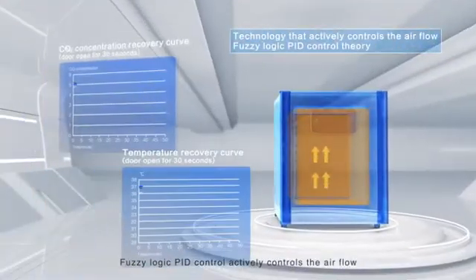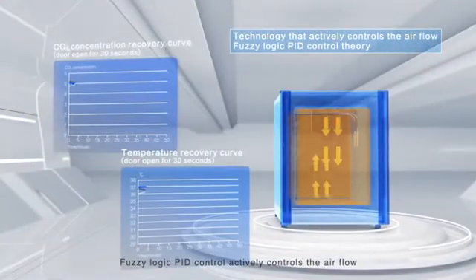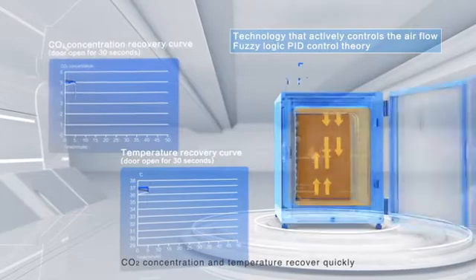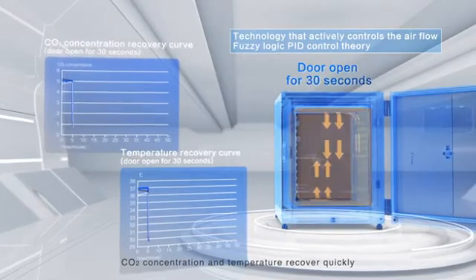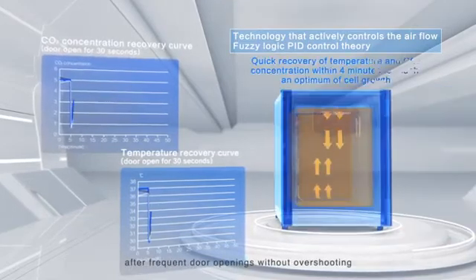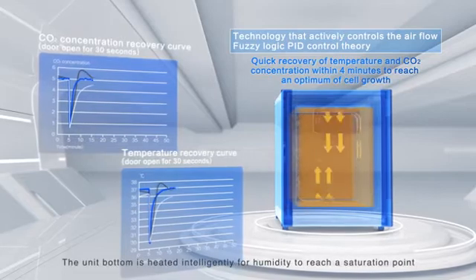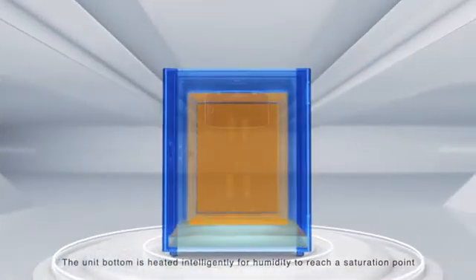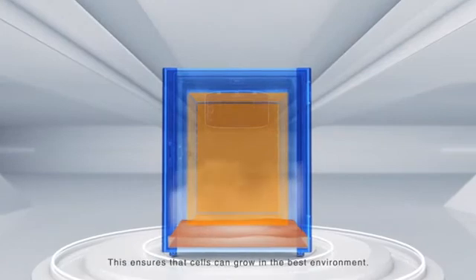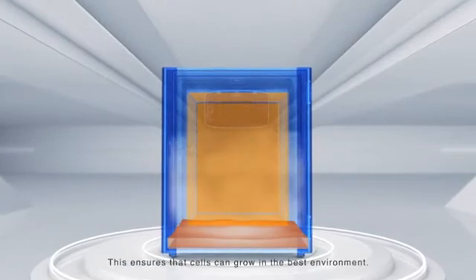Fuzzy Logic PID control actively controls the air flow. CO2 concentration and temperature recover quickly after frequent door openings without overshooting. The unit bottom is heated intelligently for humidity to reach a saturation point. This ensures that the cells can grow in the best environment.